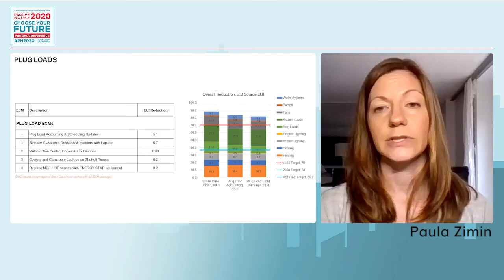Those standards are a per-square-foot standard. We said to SDA, why don't we do an accounting of all the equipment you typically put into buildings? They have a very detailed list of all the equipment they'd put into a second and third grade classroom versus a science room versus a computer room versus a gymnasium. We combined all that detailed information, applied different schedules to explicit equipment, and were able to really reduce the plug loads just by accounting for the equipment explicitly.